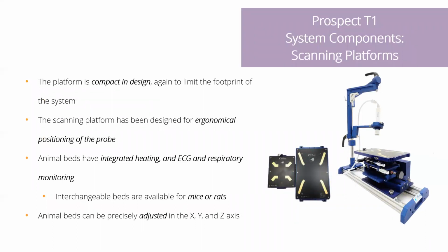The scanning platform has many different components. The first that you see here is the mouse and the rat platform. Both platforms are heated. They do have ECG leads, which allow us to obtain the ECG signal from the animal, as well as to give us respiratory signal. There is a rectal probe to give us body temperature, and that also helps in the feedback loop of the system. The probe itself is mounted into the holder and can rotate and tilt in all different directions.